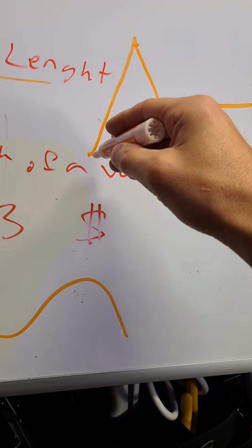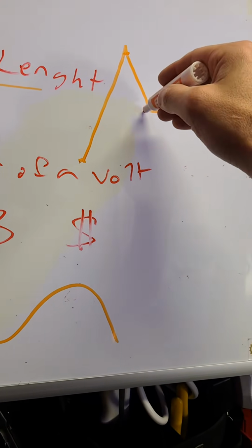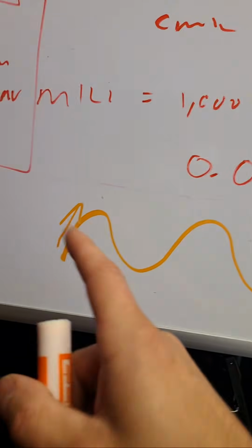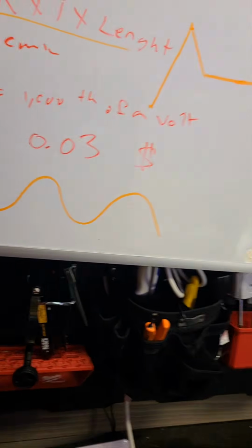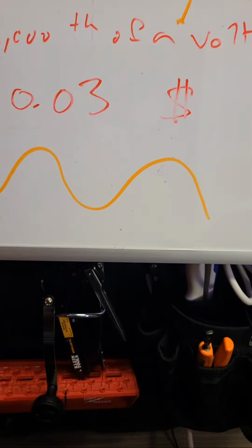So you've only got a split second to catch the inrush current before it drops down to a normal level. And not a lot of multimeters will do that. I don't know what the max amp setting is on a Fluke, but the fact that it doesn't say inrush tells me that it probably doesn't do inrush, because inrush would be like a buzzword for a selling point on something. It's possible they might have just made their own names for it.